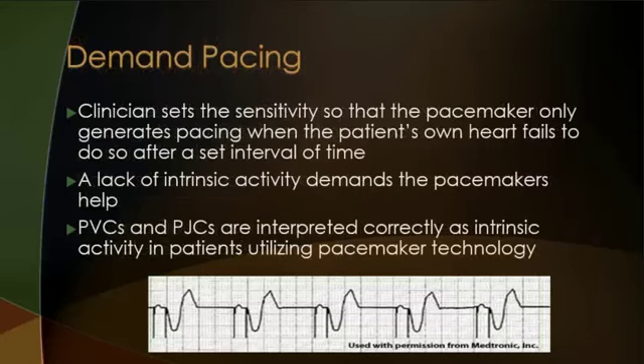So what exactly is demand pacing? The clinician sets the sensitivity so that the pacemaker only generates pacing when the patient's own heart rate fails to do so after a set interval of time. So they'll set, like, the rate at 60. If the patient's rate is 45, we'll see pacing spikes. If the patient's rate is 70, we won't see pacing spikes. If there's a lack of intrinsic activity, then the pacemaker demands help.